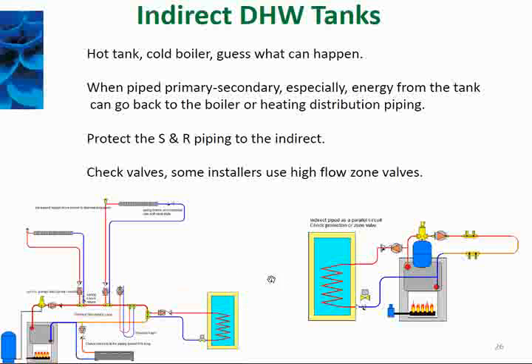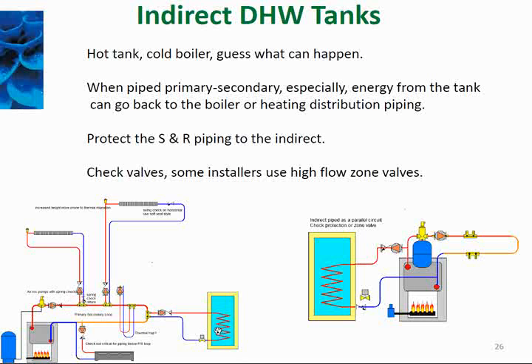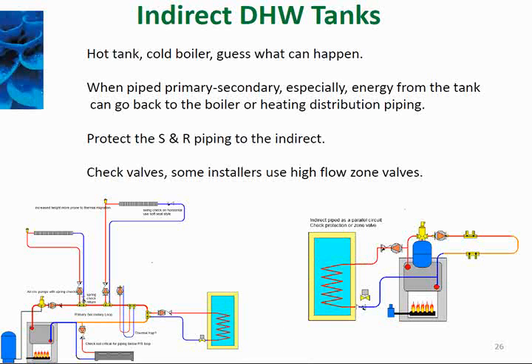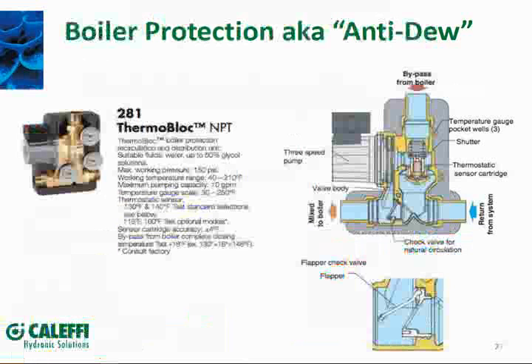We discussed thermal migration to an indirect tank off a primary loop. A cleaner approach: pipe your indirect tank as a parallel loop directly off the boiler. With primary-secondary piping, you have to run the primary loop pump to get heat to the indirect tank. Moving it to a parallel loop means you only need to fire that one pump — you don't have to heat up the entire primary loop. You still need check protection there: a spring check or zone valve, plus a check-protected pump, giving you 100% bubble-tight shutoff protection on both sides.